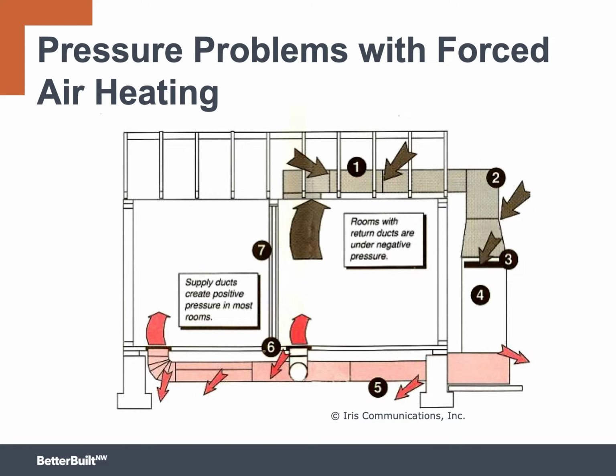Here's how it works. If you have leaks in the supply side of the system, not all the air is getting back inside the house. You're going to starve the house for air, or at least those rooms, and it's going to create a negative pressure. If there are leaks on the return side, there's extra air pulled into the ducts from the outside.